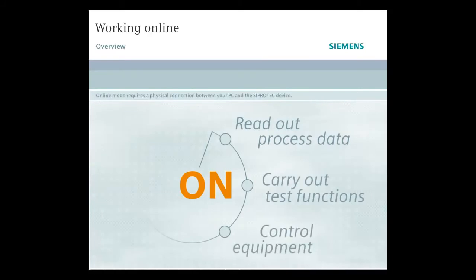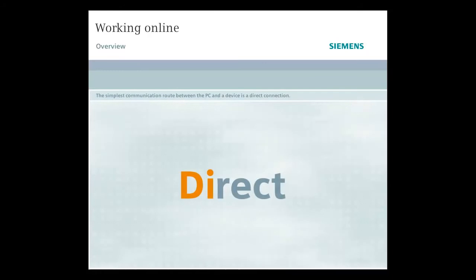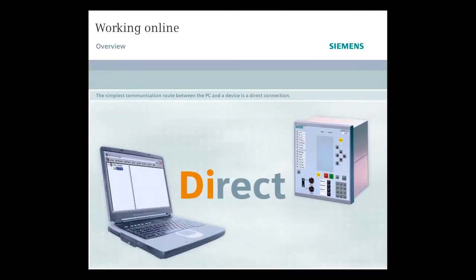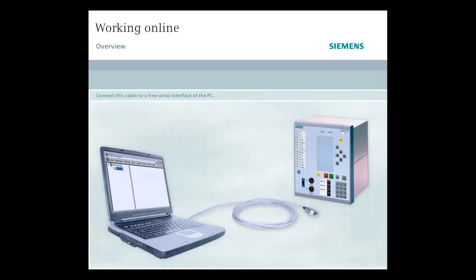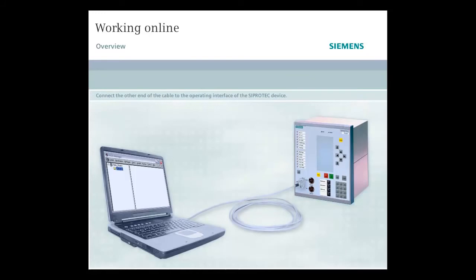Online mode requires a physical connection between your PC and the SIPROTEC device. The simplest communication route is a direct connection. All you require for this is a serial cable like the one included with DIGSI 4. Connect this cable to a free serial interface of the PC, and connect the other end to the operating interface of the SIPROTEC device.